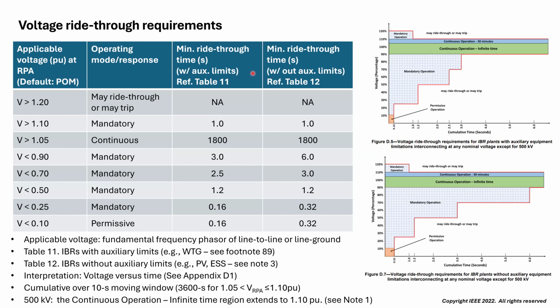So Table 11 is for those IBRs that have IBR units that may have auxiliary limitations. The example thought of here was IBRs with wind turbine generators, some of the larger motors they may have. And a full explanation of that is in footnote 89. Table 12 is for those IBR plants that have IBR units without auxiliary limitations. So this was more thought of as PV or battery energy storage type IBR units, as stated in note 3.